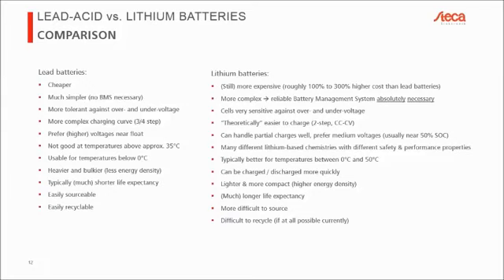Whereas a lead battery, if you overcharge it, it will simply gas hydrogen and oxygen, which, if you have a very small room, can be dangerous because it's obviously explosive. But in most size rooms, you will never reach a level of hydrogen high enough to cause any problems. And if you deep discharge a lead battery, well, then it will simply die slowly. It will lose capacity. If you deep discharge a lithium battery and then recharge it, then it is actually much more prone to catching fire, exploding, or venting.